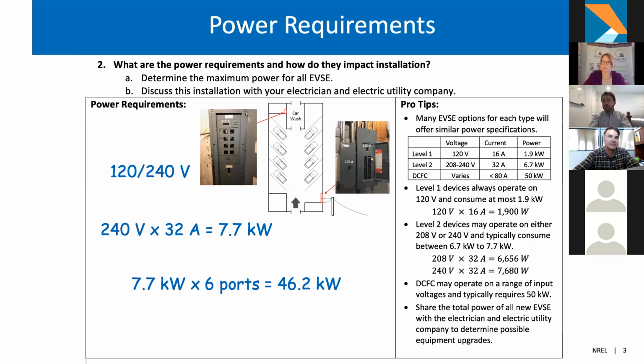So then if you increase the load such that if all the EVSE are on at one time it goes beyond 150 amps, most likely your electrician will recommend upgrading the service panel or potentially having 2. At that point, that's when you'll need to work with your utility company and talk to them about the new increased load.